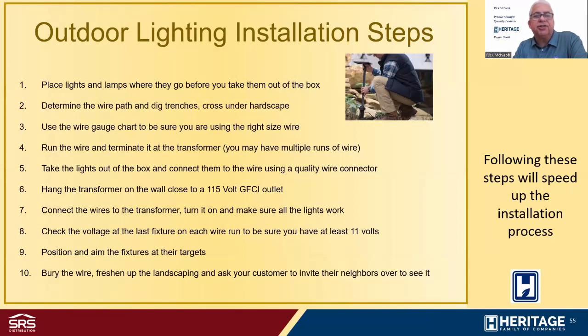Step 3, use the wire gauge chart to be sure you are using the right size wire. So yeah, take out your wire gauge chart that you've made a copy of and take a look at the property, measure with your measuring wheel how far your wire run is, figure out how many watts are on that cable or on that wire run, and use the wire chart to make sure you're using the right size cable for that circuit. And then install the wire, run that wire and terminate it at the transformer.